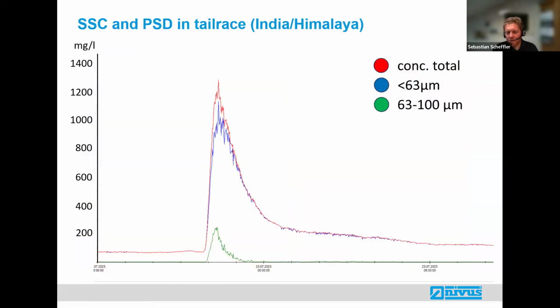What we can see here is some measurement data of this measurement site. First, the red curve again shows the total concentration. We have a very low concentration of round about 80 milligrams per liter. Also, the red curve indicating total concentration lies above the blue curve, meaning almost all the sediments consist of very fine particles, finer than 63 micrometers.